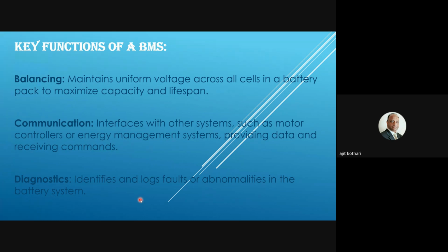Similarly, in case of discharge, let's say one cell is completely discharged at 0%, but the other 9 cells have a charge of 100%. Then that battery bank cannot be used for discharging purpose, because one cell is not giving current, since all cells are connected in series. So that bank is useless - I cannot use it for charging purpose, I cannot use it for discharging purpose. If a cell is not charged, I cannot discharge it. If one cell is fully charged and others are not, I'll not get the full capacity from the battery bank because other cells are not charged fully, and I'll not be able to charge the battery bank because one cell being fully charged won't allow me to charge the remaining cells. So balancing of all the cells is very important.